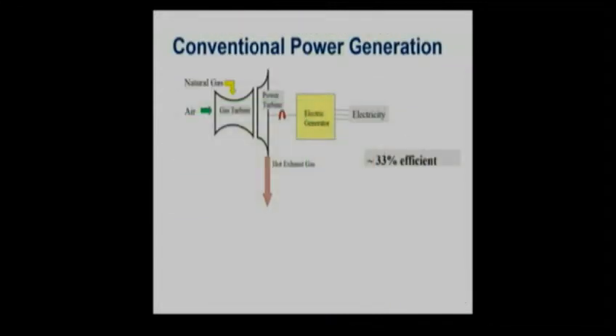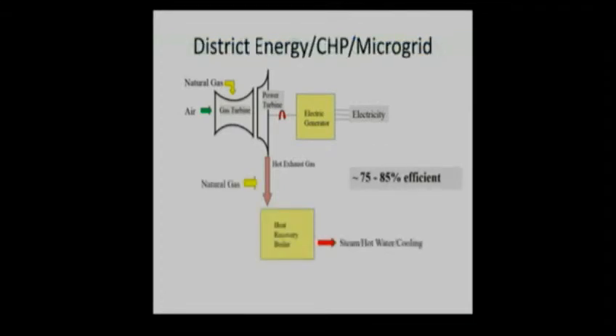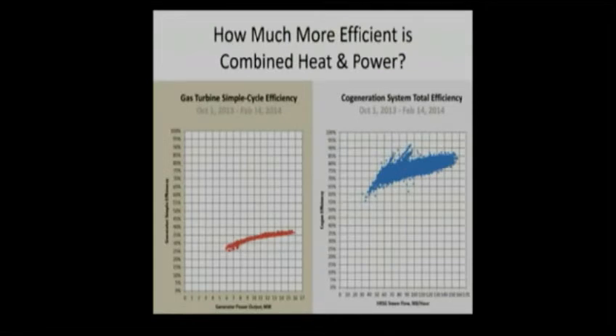If this were just a conventional jet engine turbine, it'd be producing power at about 33%. But because they recover the heat at Princeton and use it to make chilled water as well as heat for the campus, they're operating at efficiencies of nearly 85%. Their simple cycle gas turbine efficiency is 37-38%, but by recovering the heat, they're now getting 80-85% use of the fuel they consume for the campus.